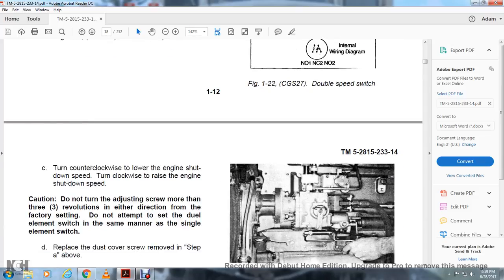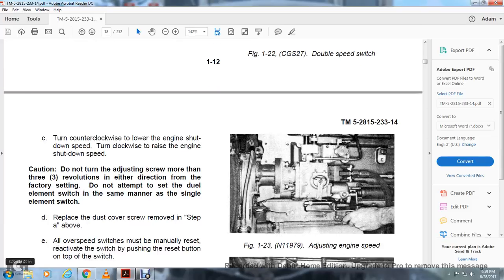Turn counterclockwise to lower the engine shutdown speed. Turn clockwise to raise the engine shutdown speed. Do not turn the adjusting screw more than 3 revolutions in either direction from the factory setting. Do not attempt to set the dual element switch in the same manner as the single element switch.